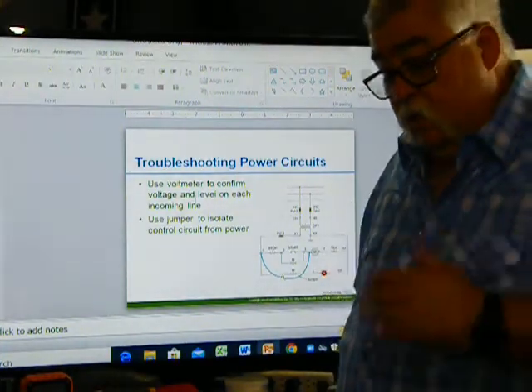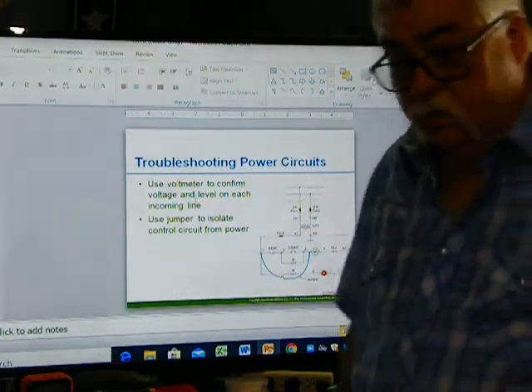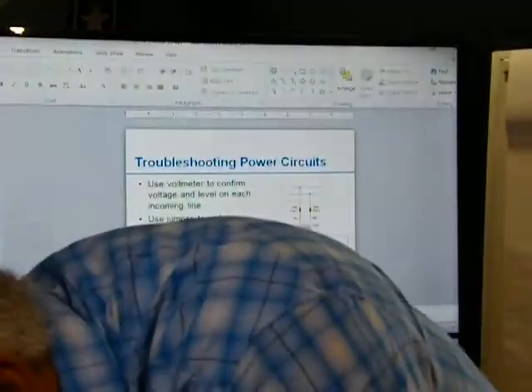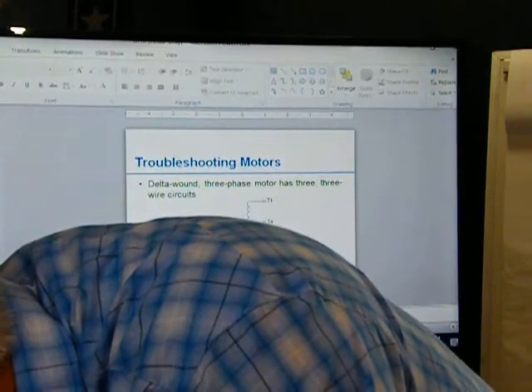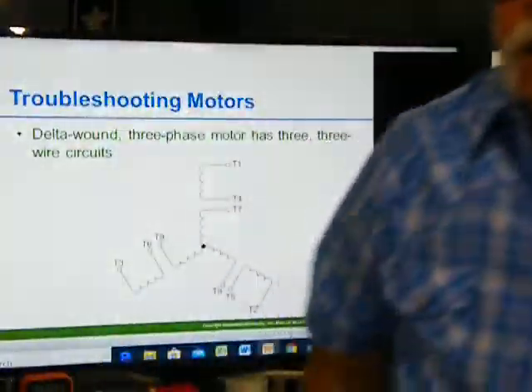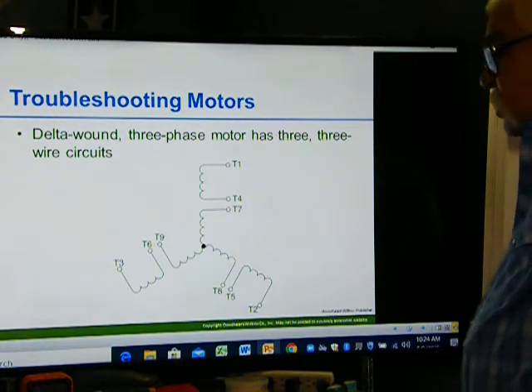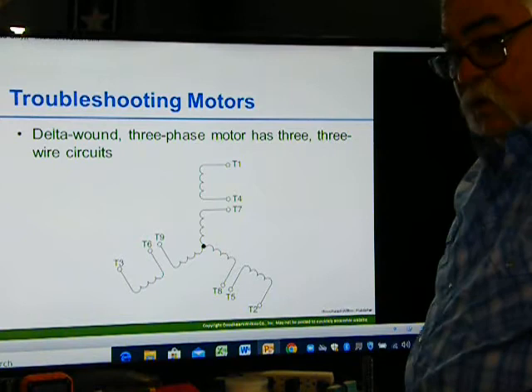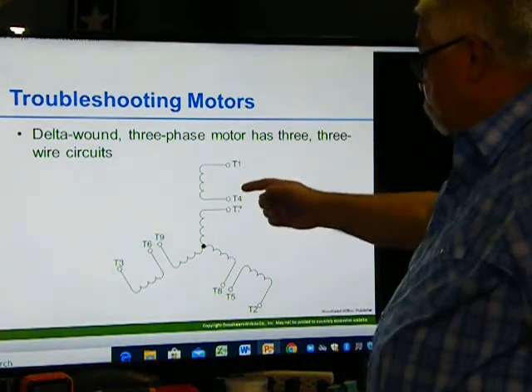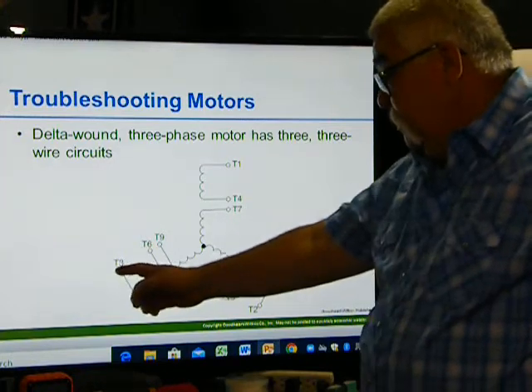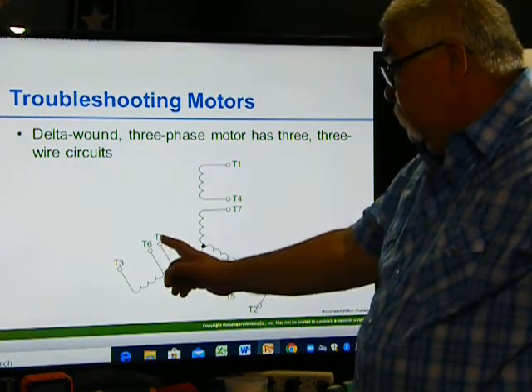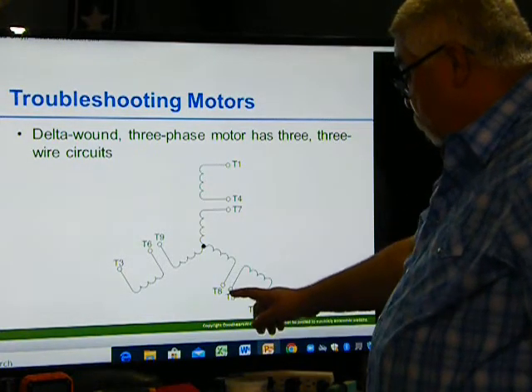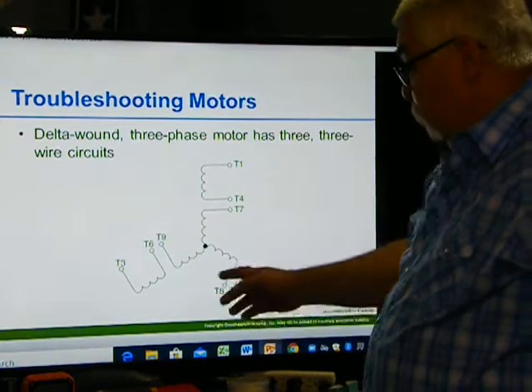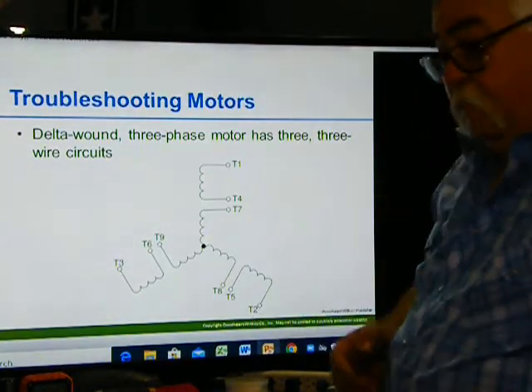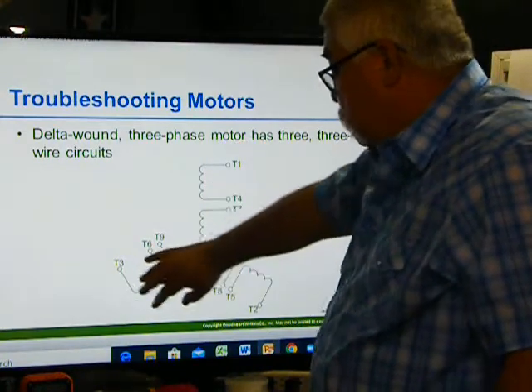So depending on our voltage, we know our 3 windings. If you pay attention to the windings, let me go back over here real quick. Notice what's a common thread in all of this? They're all multiples of 3. 1 plus 3 is 4. 4 plus 3 is 7. 3 plus 3 is 6. 6 plus 3 is 9. 2 plus 3 is 5. And 5 plus 3 is 8. So they're all common in these windings, so it's easier to pair them up. You may not have this one or this one done.